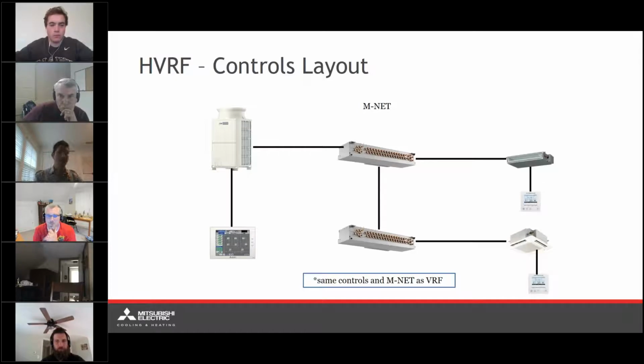Mike, what would be the difference between the controls on that versus the HEX system? Yes. So, again, the HEX unit is just registered on the City Multi VRF system as another indoor unit. So when you connect the communication wire from the main BC to the HEX unit, it's going to be the same exact connection you see here between this BC and this fan coil. It's just a single point connection. Obviously, there are hardwired points on the HEX unit as well for a little more customized control. We can have water loop temperature adjustments based on an analog electrical signal output to the HEX unit. But again, the HEX unit is just single point communication wiring, daisy chained throughout the system.